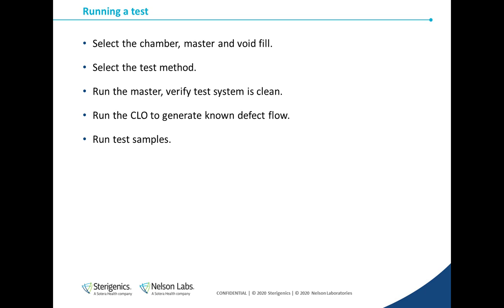The first step in testing is to make sure that the instrument is free of residual mass. Remember that any mass in the system will look like a leak to the instrument, so we verify that the system is clean and dry by running the master. We know the master can't leak, so if the master fails the test, then we need to clean the system. Once the master passes, then the system is ready to go.